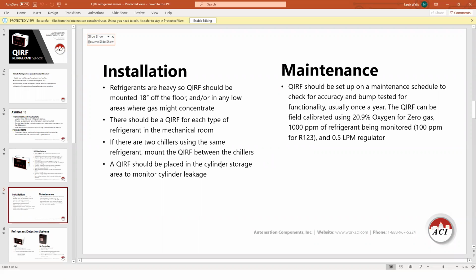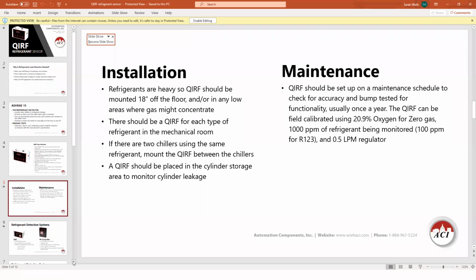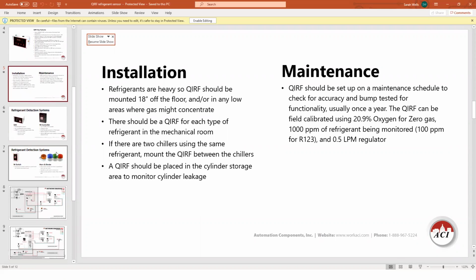Yeah, usually the devices should be checked, with a calibration check and bump test once a year with whatever refrigeration gas is being used. We recommend using 20.9% oxygen for the zero gas. Do not use anything nitrogen based or with a nitrogen balance, because that is a heated infrared sensor, and nitrogen comes out pretty cold, and it can damage the IR sensor. So make sure it's 20.9% oxygen for your zero gas.